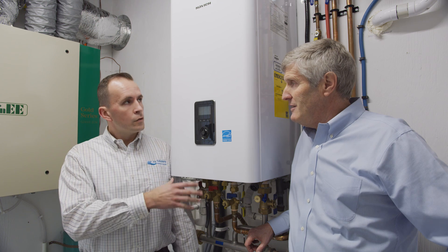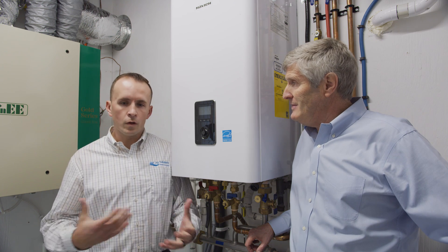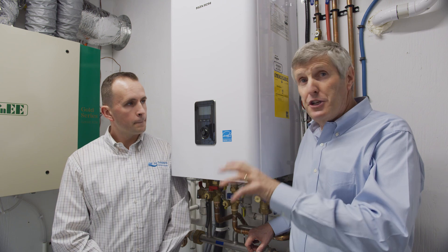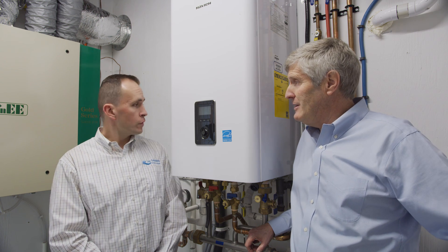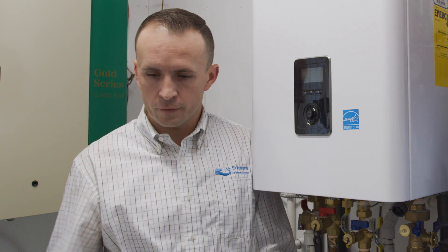So we have here our new NFC — the fire tube combi. A fire tube based heat exchanger tends to be a little bit more robust versus your traditional water tube type heat exchangers, lending to the resiliency, longer service life, a little more forgiving from a design perspective as well. But truly it's one appliance for the whole home — it's doing both the domestic hot water, and we've got a ton of showers here with a big family, and we're also doing the in-floor heating off of this. This particular model will give you 200,000 BTUs of heating, more than adequate for lots of in-floor and maybe some snow melt if you ever wanted to do that.